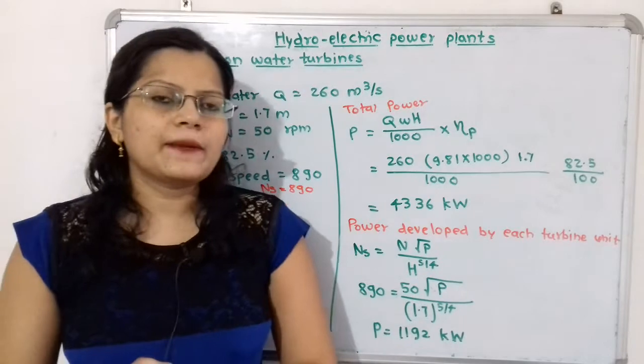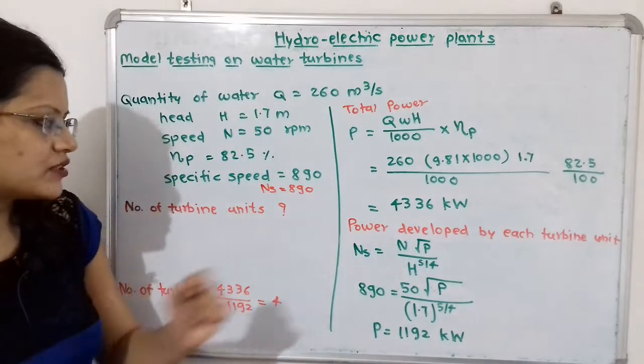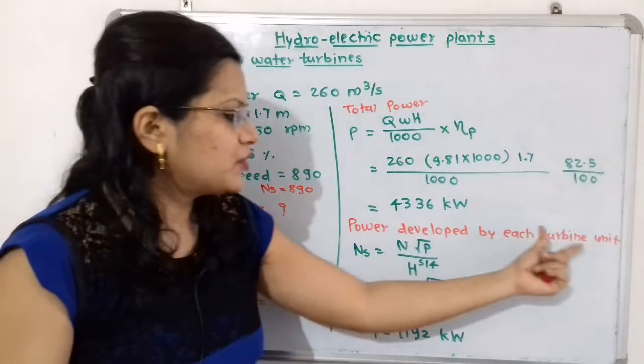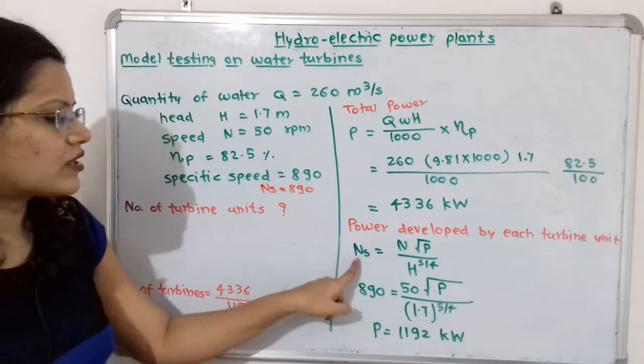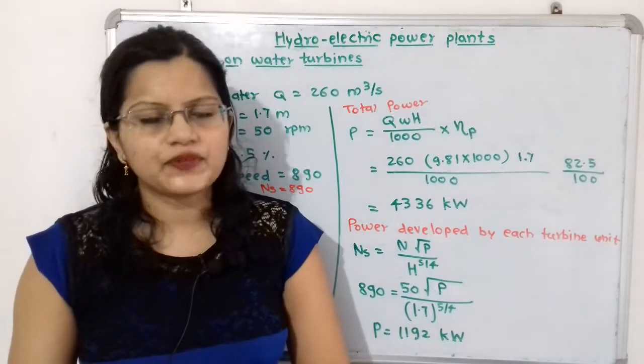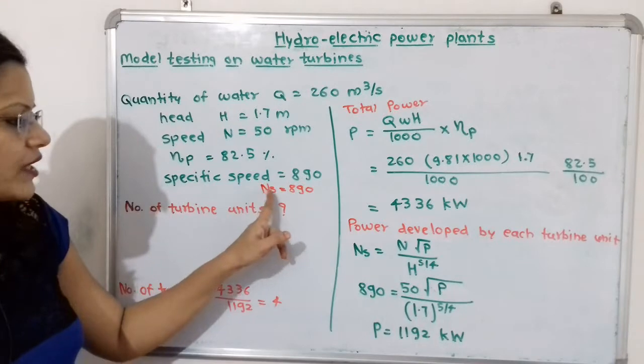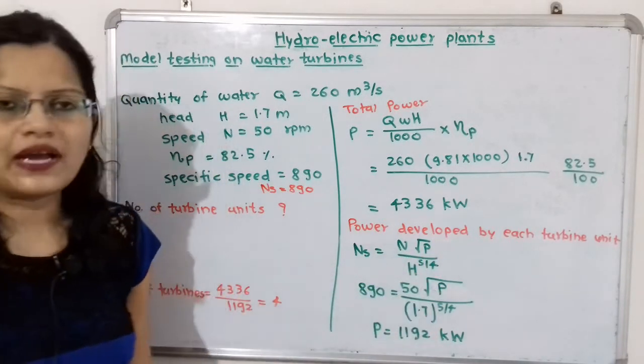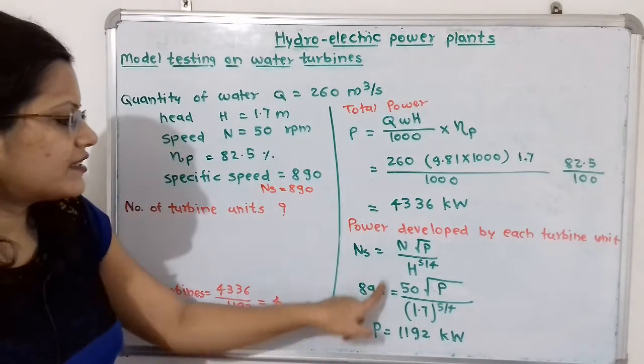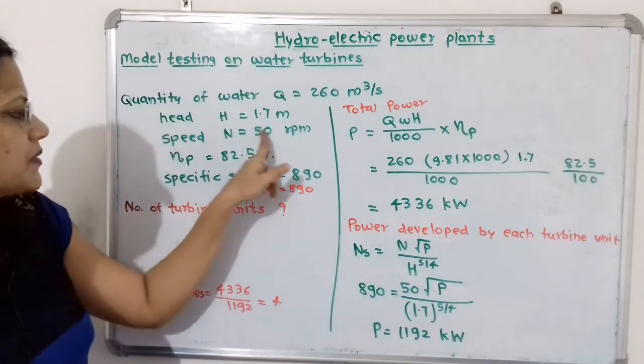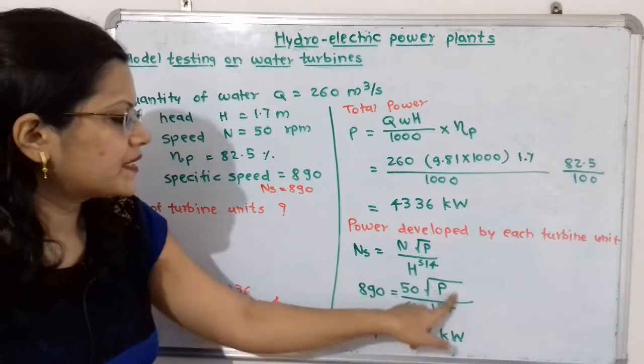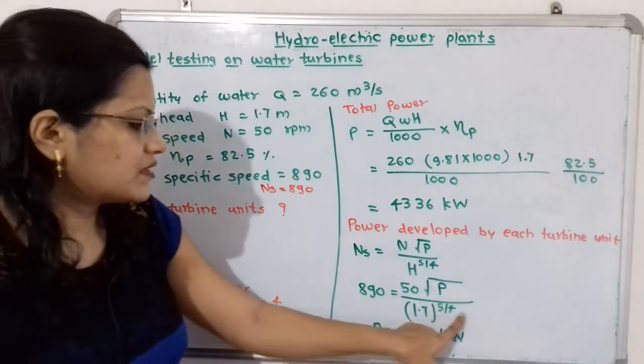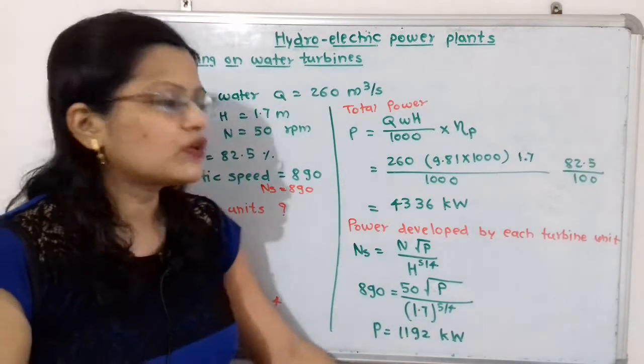Now we calculate the power developed by each turbine unit using the specific speed formula. Specific speed N_S = N × √P / H^(5/4). Substituting: 890 = 50 × √P / 1.7^(5/4). Solving for P, the power developed by each turbine unit is 1192 kilowatts.